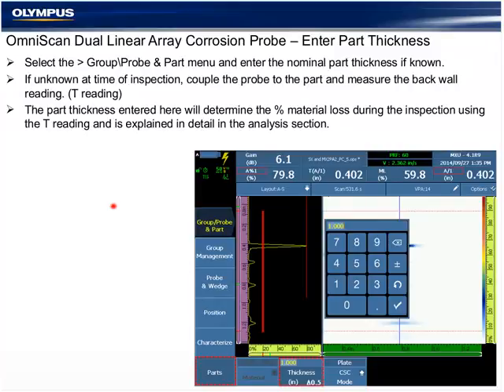So the part thickness can't be known prior to entering the configuration files, so it must be adjusted for each one. Under the probe part menu, under thickness, enter the nominal thickness of the part. You may or may not know it at the time of the inspection, and this can be changed in analysis mode at any time. This thickness is going to affect our skip lines in the data, and it's also going to affect our material loss reading that we'll learn about. It's very simple math: based on the current thickness and the component thickness, the software calculates a material loss percent. And again, it can be changed at any time before or after the inspection. Part thickness.